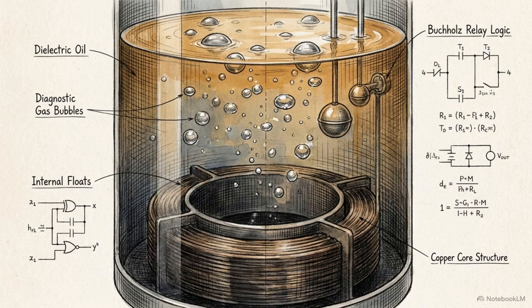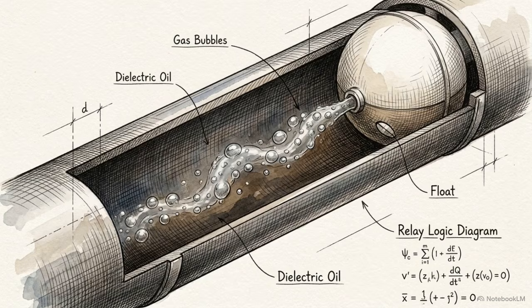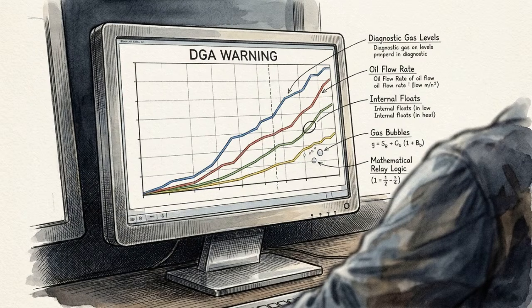Because these gases are significantly lighter than the cooling oil, simple physics takes over. The bubbles naturally travel upward, flowing through the primary piping toward the external overhead conservator tank. Tracking these specific chemical byproducts provides the earliest possible warning system. It allows engineers to catch impending failures before they cause irreversible damage.